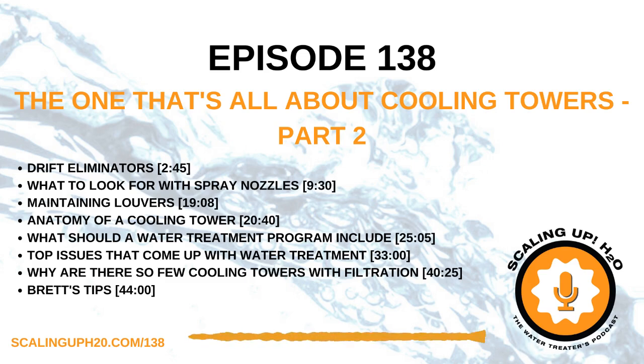Yeah, that's important also, because you need to take the drift eliminators off, as you mentioned, to see the spray nozzles, because there are different spray nozzles, and some are more prone to getting clogged up. And that's a concern, right? Because we know from a water treatment chemistry standpoint, if you're not getting adequate spray coverage over that fill, you're going to be more prone to having a wet-dry surface. And then you'll see deposits start forming, right? Scale, if it's not continuously wet in that area.